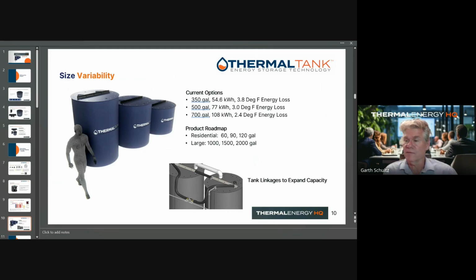Well, number one, the real estate—where am I going to go put this thermal storage system? Aside from the capability of being able to walk the parts into that boiler room or locate outside on a rooftop, we've built up structures from 700, 500, and 350 gallon on a common 5-foot, 60-inch diameter footprint, so that we can match your space needs and your space utilization. If you have all the space in the world and you need large thermal storage, then the 700-gallon tank will work. We also have the capability of chaining these, joining them fluidically together, in order to give you expanded capacity: 700, 1400, 2100 gallons, and so on, in order to match your energy storage needs.